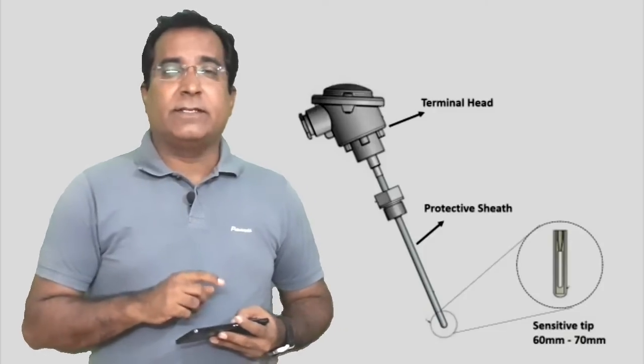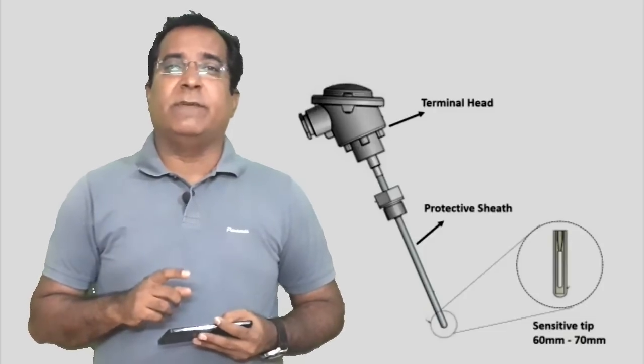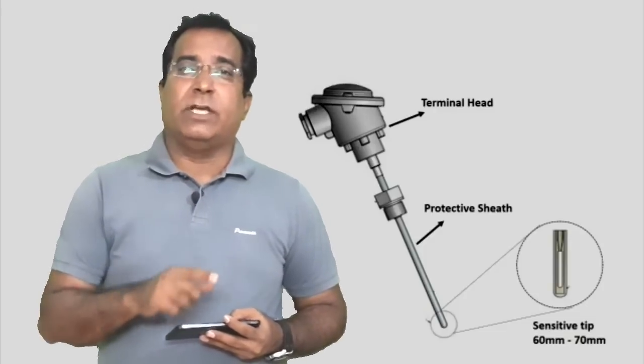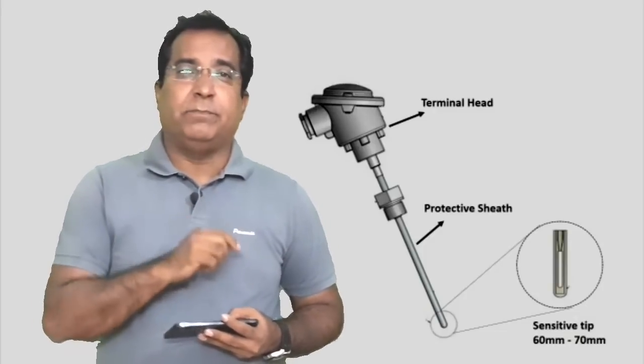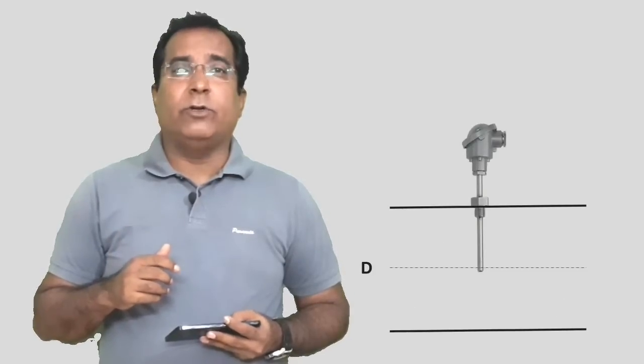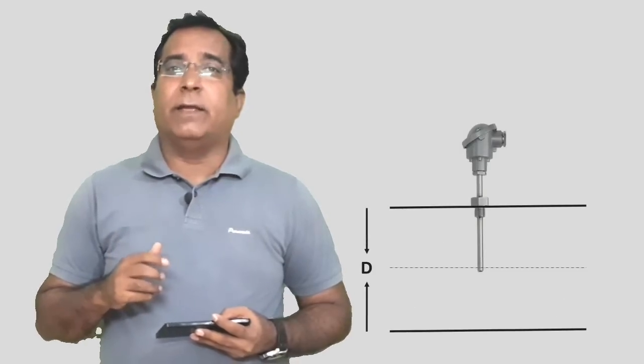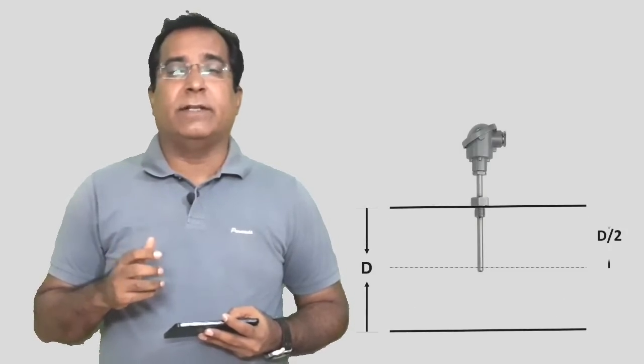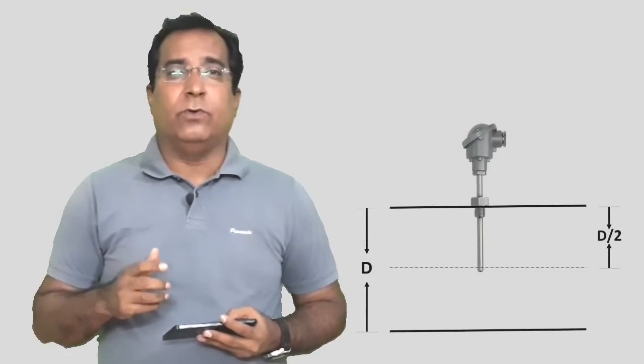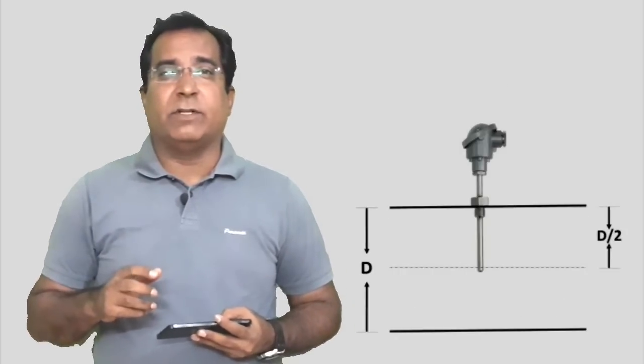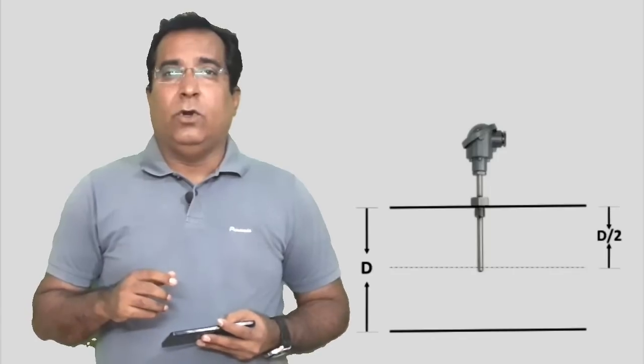And second concern is how much sensor must be inserted in process or pipe. So thumb rule is up to the central line of the pipe. Suppose you have pipe dia of D and now you have to keep insertion D by 2 of the RTD or the thermocouple sensor.